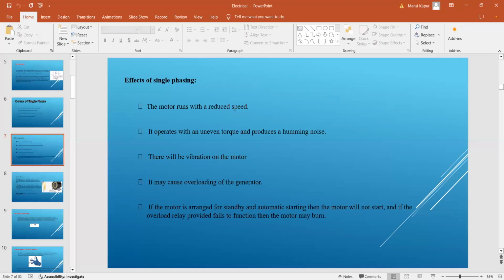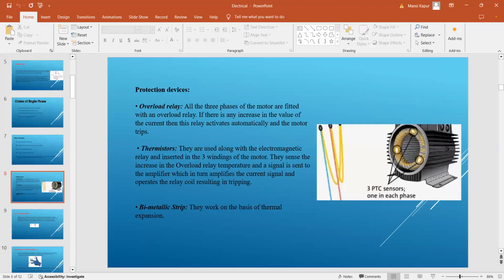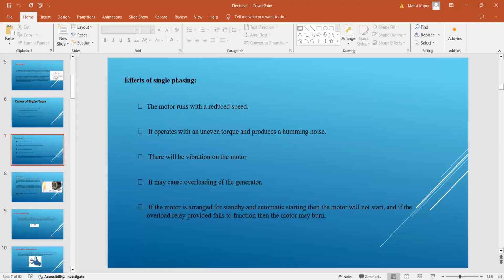As you said correctly before also, there will be a reduction in the motor speed. It operates at uneven torque and produces a humming noise and sound. It is going to vibrate. It is going to overload the generator, not necessarily. For the motor arranged for standby and automatic starting, the motor will not start, or if it does start, that is your luck. And if the overload relay provided fails to function, then the motor is going to burn. Okay, these all can be the effects of single phasing.